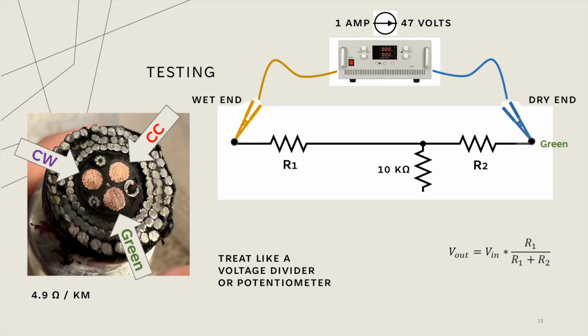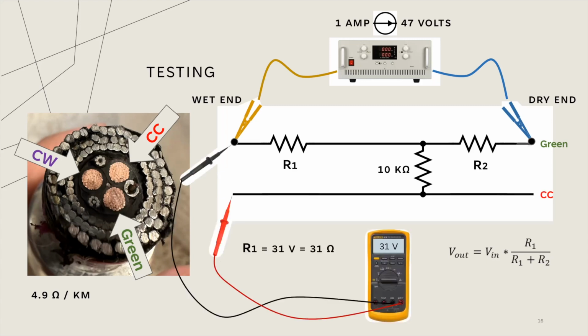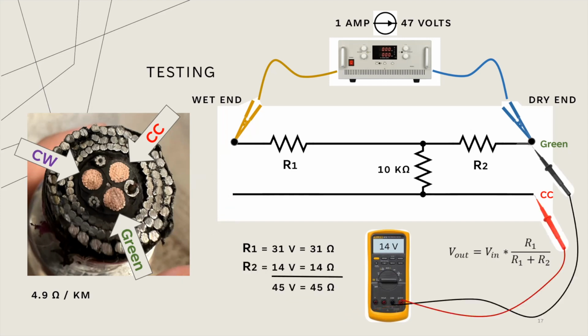So we attached a power supply to one of the bad conductors and sent 1 amp current through the conductor. 1 amp made all the math a lot easier. The resistance of the whole cable was 47 ohms, so our power supply charged at 47 volts. Then to get our V out, we measured the conductor adjacent to it, included in the fault, with our multimeter. On the wet end first, we got 31 volts, which with 1 amp is 31 ohms. We measured the dry end and got 14 volts, for a total of 45 volts.